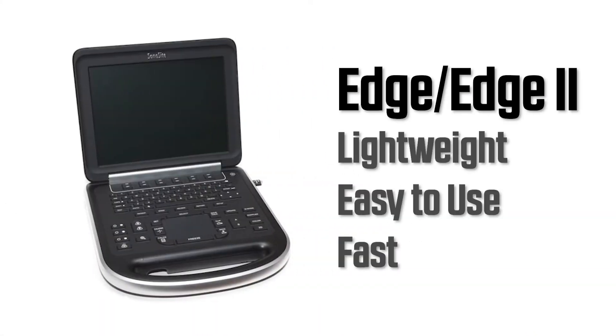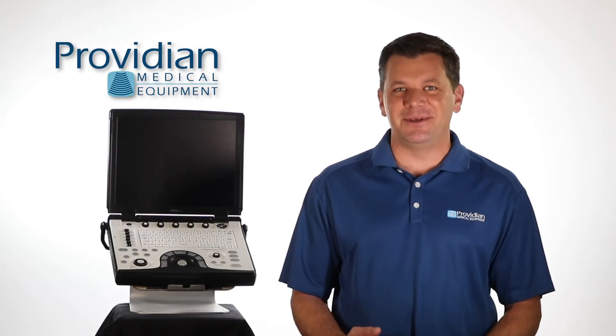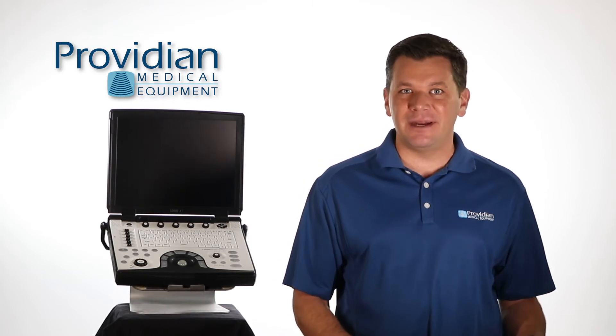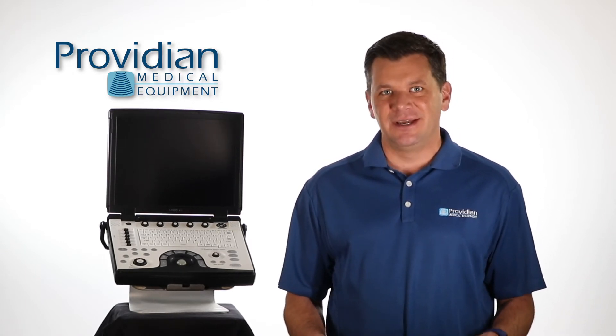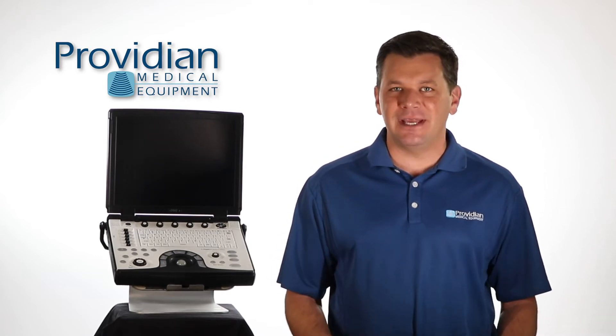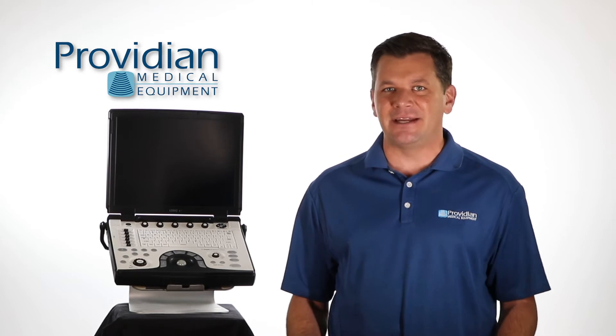In fact, the most common questions physicians ask me about a point-of-care system are image quality, ease of use, and speed. While the Next-Gen has great image quality and it's very fast once it's booted, the boot time is still 60 seconds, which is three to four times slower than Sonosite's machines. Additionally, the Sonosite is much easier to use, particularly for those needing a visualization tool and not a full diagnostic ultrasound machine.